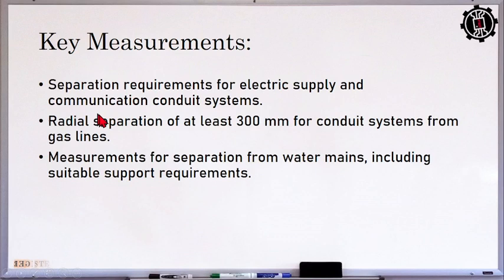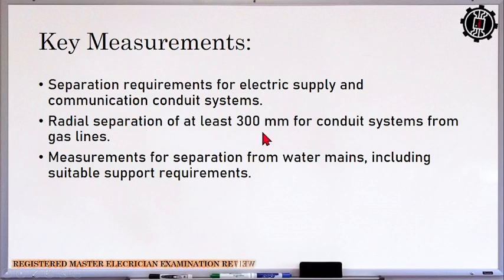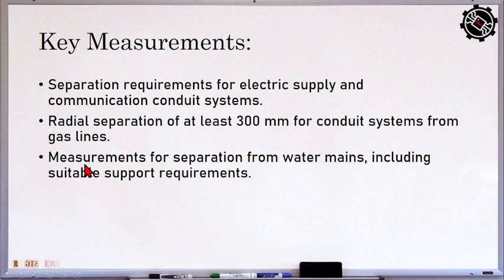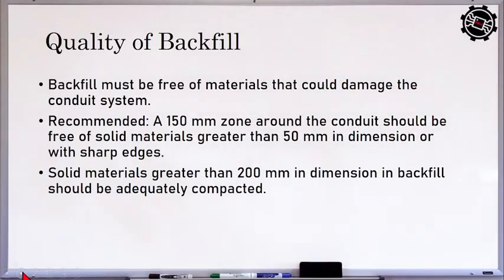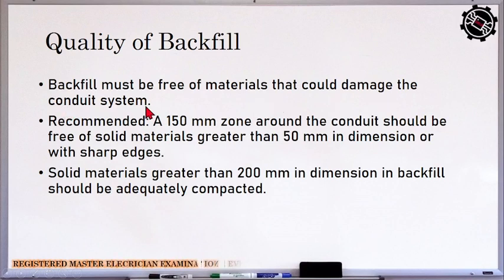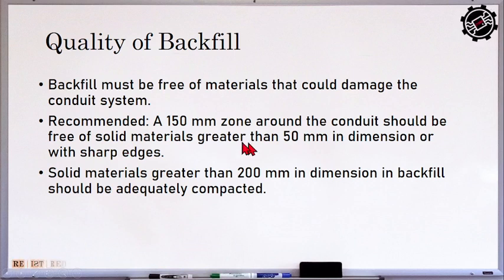So key measurements, so separation requirements for electrical supply and communication conduit system. Then the radial separation at least 300 mm for gas lines. Tapos measurements for separation from water mains including suitable supports requirement. Then the quality of backfill. So backfill must be free of materials that could damage the conduit system. So dapat yung itatabo natin sa ating conduit must be free from materials na pwedeng ma-damage yung ating conduit. Then recommended 150 mm zone around the conduit should be free of solid materials greater than 50 mm in dimension.